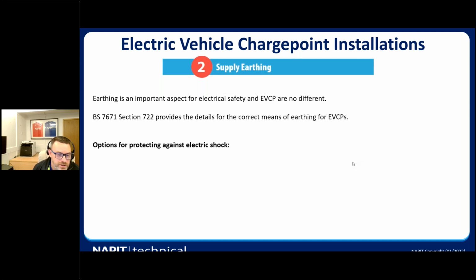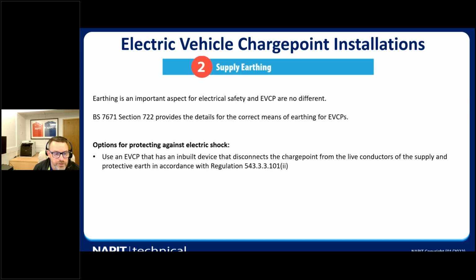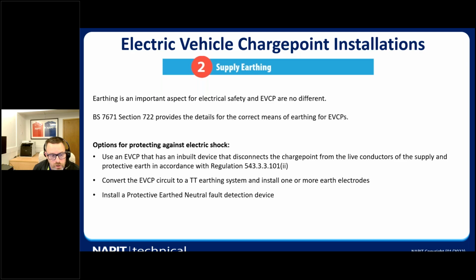The options for protecting against electric shock are using an EVCP with an inbuilt device that disconnects the charge point from live conductors and supply protective earthing, as in regulation 543.3.3.101 (2). Convert the EV charge point to a TT system, install one or more earth electrodes, or install a protective neutral fault detection device to make sure in the fault of an open PEN conductor the EV installation is disconnected from the source.